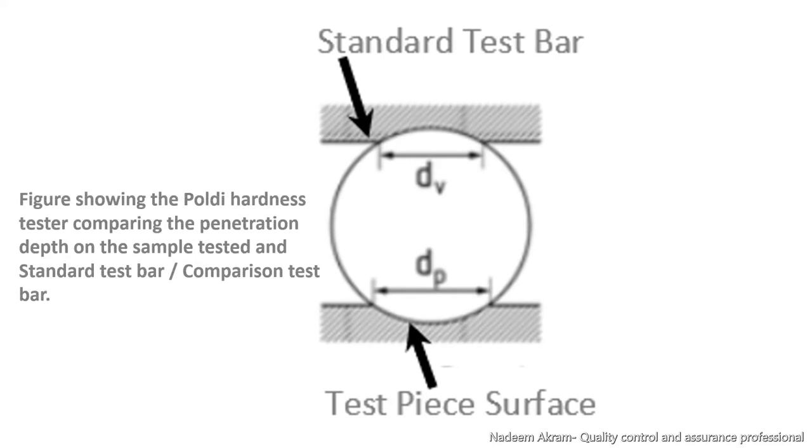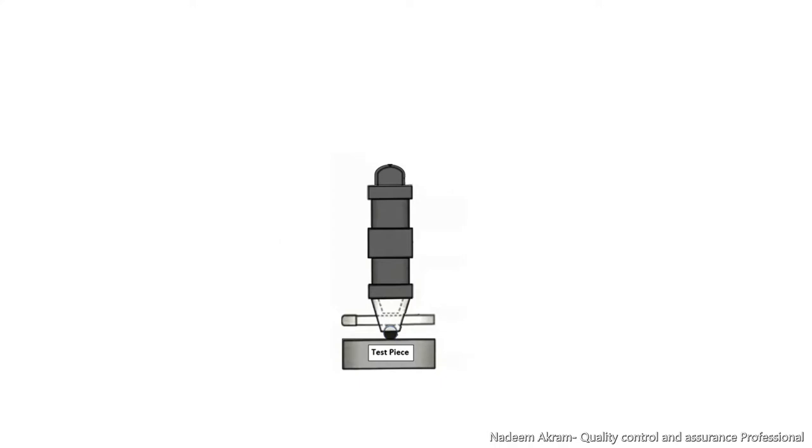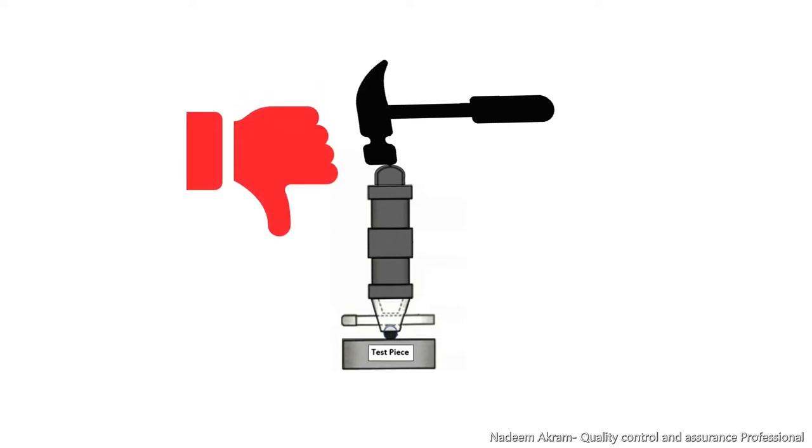It is essential to apply a well-guided, short blow to avoid a rebound and thus a double blow that may produce an erroneous result by damaging the sharp edge of the ball impression.